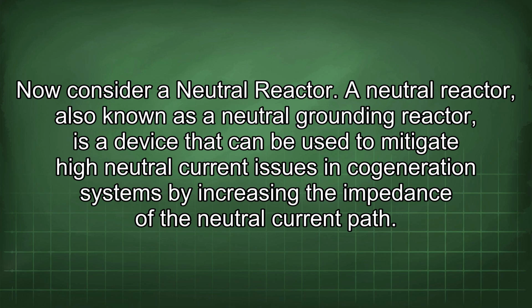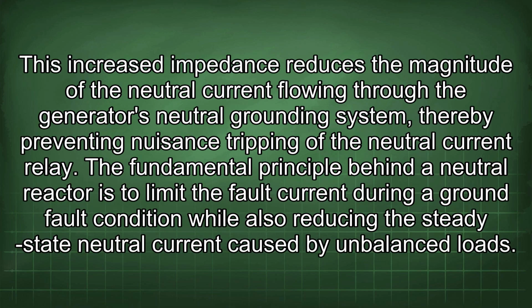A neutral reactor, also known as a neutral grounding reactor, is a device that can be used to mitigate high neutral current issues in cogeneration systems by increasing the impedance of the neutral current path. This increased impedance reduces the magnitude of the neutral current flowing through the generator's neutral grounding system, thereby preventing nuisance tripping of the neutral current relay. The fundamental principle behind a neutral reactor is to limit the fault current during a ground fault condition while also reducing the steady-state neutral current caused by imbalanced loads.